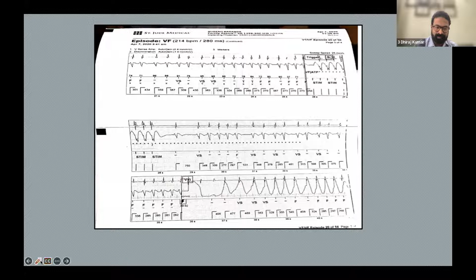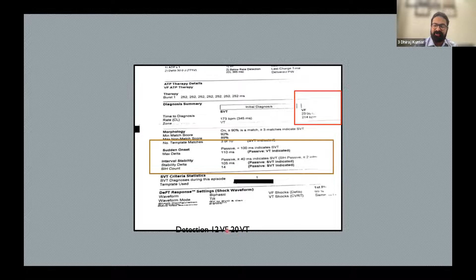So we looked at the baseline programming. We looked at the VF zone being set at 214. That is coming out to be a cycle length of 280. And we looked at discriminators. All the discriminators were disabled. So sudden onset and interval stability. Okay, and detection was only for 12 for VF and 20 for VT. So what is the conclusion? This is nothing but an atrial fibrillation with a fast ventricular rate. It is misclassified as ventricular fibrillation, and that is why the device delivered therapy.